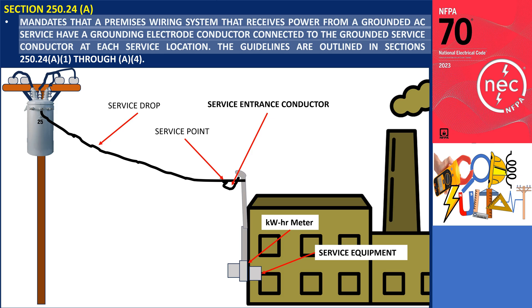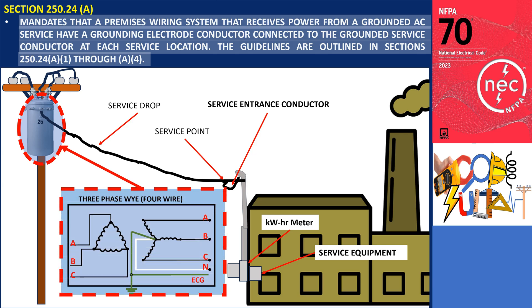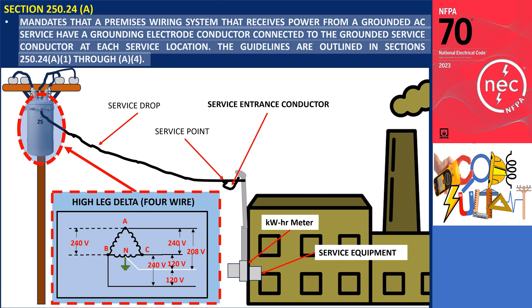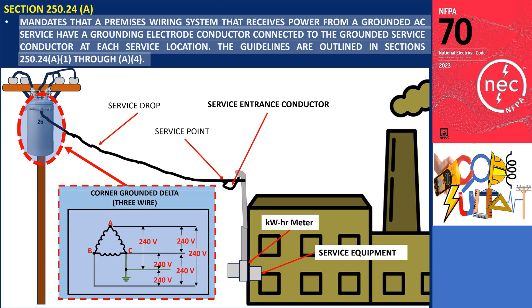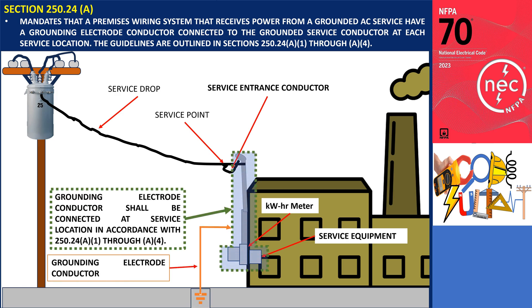The guidelines are outlined in Sections 250.24(a)(1) through (a)(4). If the premises wiring is supplied by a service AC system — such as a single-phase 3-wire system, a three-phase Y 4-wire system, a high-leg delta 4-wire system, or a corner-grounded delta 3-wire system — the grounding electrode conductor should be connected at the service location, following the guidelines in 250.24(a)(1) through 250.24(a)(4).